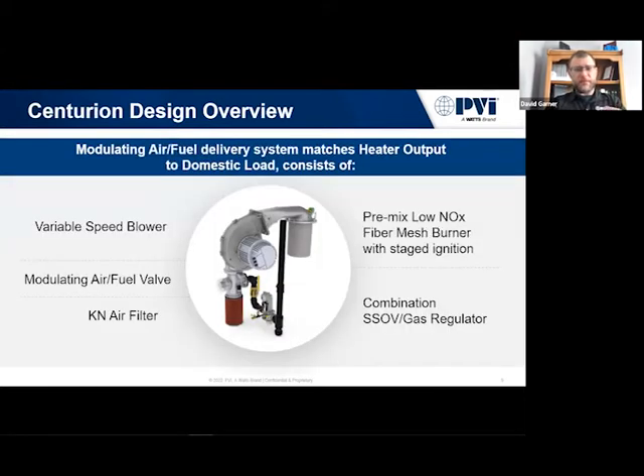When we look at the combustion system, just following the pipe here, this is our gas supply coming into our SSOV, which is the safety shutoff valve. That's going to connect to the air fuel valve. On the air side, we have a K&N air filter, same one that everyone uses on their trucks. You pick up at an advanced automotive parts store, and the air and fuel is going to mix inside of the air fuel valve, go into our blower, which is the pre-mixed combustion gas, and then go into the burner.